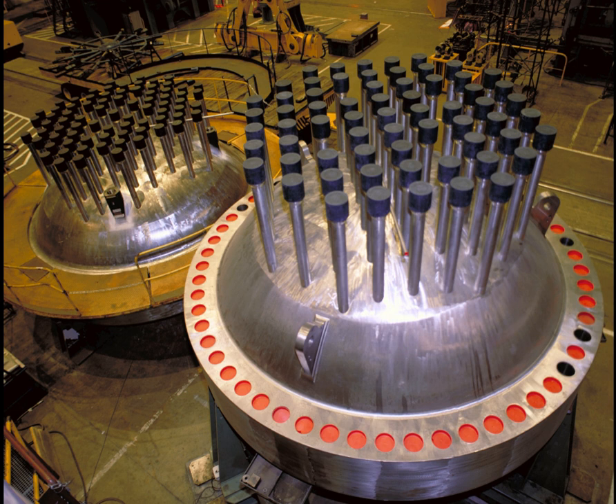Generally, the fuel bundles consist of fuel rods bundled 14×14 to 17×17. A PWR produces on the order of 900 to 1,600 MWe. PWR fuel bundles are about 4 meters in length. Refueling for most commercial PWRs is on an 18 to 24-month cycle. Approximately one-third of the core is replaced each refueling, though some more modern refueling schemes may reduce refuel time to a few days and allow refueling to occur on a shorter periodicity.